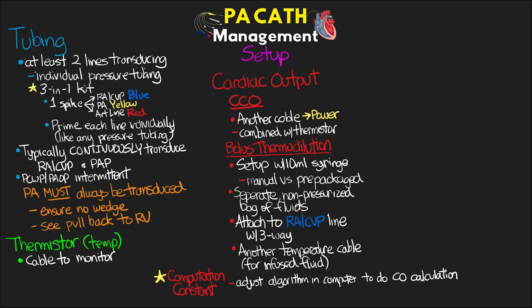So this computation constant actually factors in the size of the catheter, as well as the starting temperature of the fluid that's being infused, to ensure that the algorithm calculates the correct cardiac output. So make sure you get that inputted in there, and when you're coming onto your shift, you want to verify that this number is correct in your monitor. Now again, this only applies if you're doing the intermittent bolus thermodilution. If you're using a continuous cardiac output Swan, that already factors in everything that it needs to know.